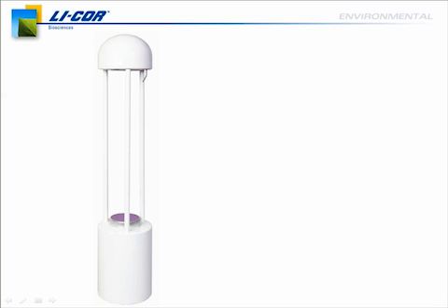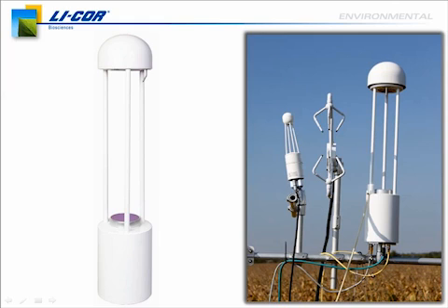It has 5 part per billion resolution at 10 Hertz, and it has user-selectable bandwidth of up to 40 Hertz. So it's a very precise and very high-speed instrument that's really ideal for deployment in the field. It weighs about 11.5 pounds, and so it's pretty easy to get out and get installed in the field. And then one of the most important characteristics of the instrument is its low power consumption.